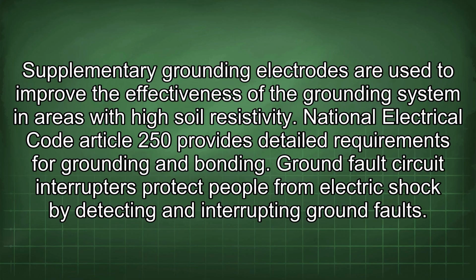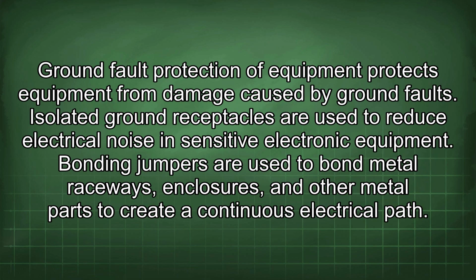Ground fault circuit interrupters protect people from electric shock by detecting and interrupting ground faults. Ground fault protection of equipment protects equipment from damage caused by ground faults. Isolated ground receptacles are used to reduce electrical noise in sensitive electronic equipment. Bonding jumpers are used to bond metal raceways, enclosures, and other metal parts to create a continuous electrical path.